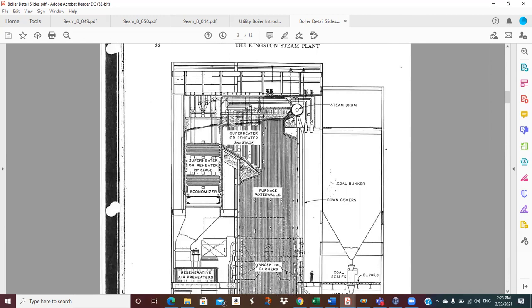These boilers are actually suspended from the ceiling, which is kind of interesting. A big boiler, from when it's cold to when it's hot, will grow in length because it expands when it gets hot. It'll expand 6 inches to a foot, maybe a foot and a half, depending on how big the boiler is and what the temperatures are. You can't let it sit on the ground because it's so heavy, when it starts growing it's just going to distort. So they're suspended from the top of the plant, and when it gets hot, it grows downward.